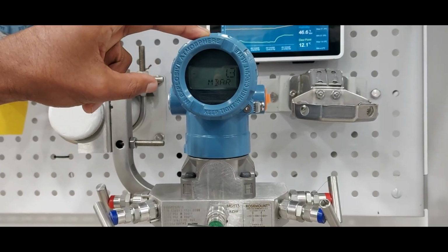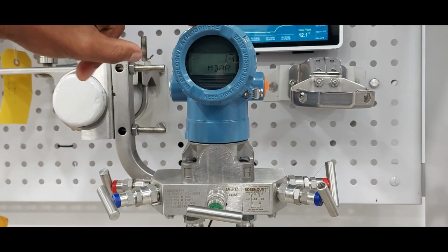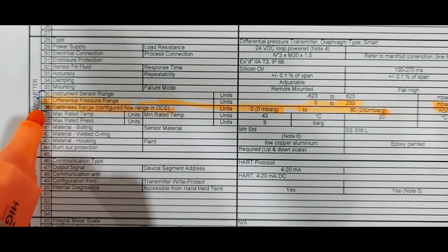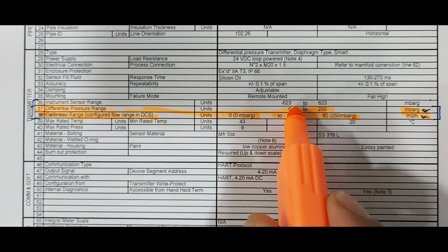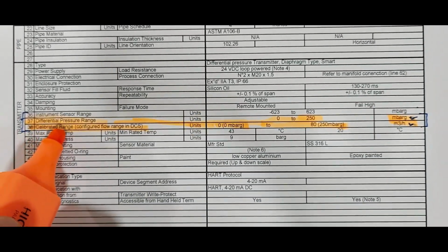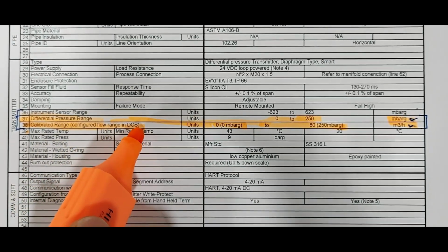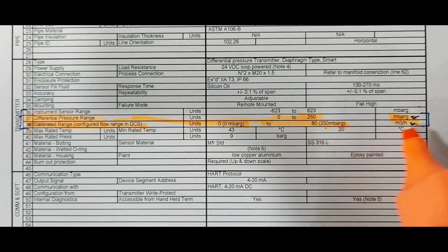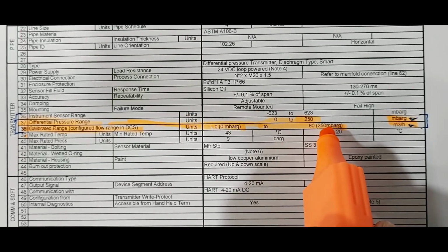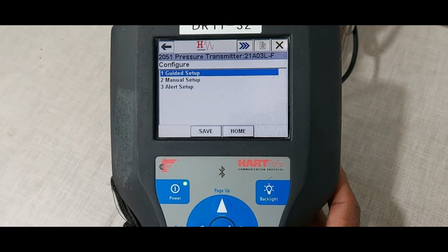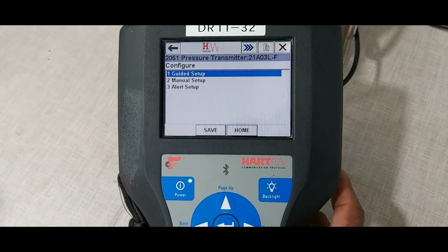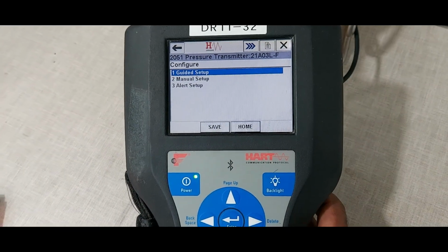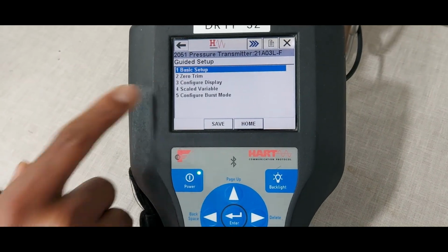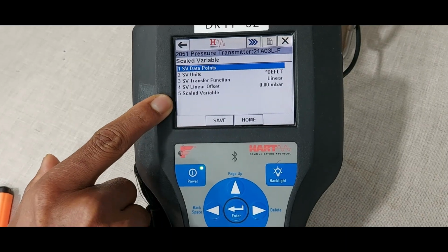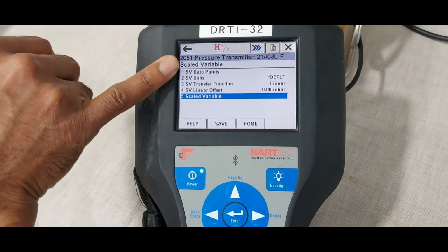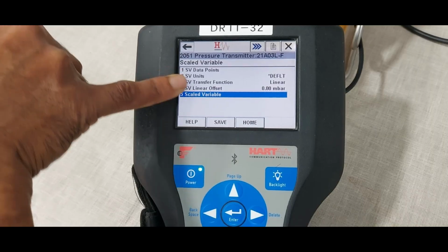Next we are doing the procedure for transmitter configuration, flow configuration and engineering configuration. The flow transmitter DP range 0 to 250 millibar. Calibrated range and configuration range of DCS: flow range is 0 to 80 meter cube per hour, DP range is the same 0 to 250 millibar. Next we are doing the configuration procedure, scaled variable. First select the configuration menu and select guided setup, and the fourth one, scaled variable unit, select it, and the fifth one, scaled variable. Default already mentioned, linear. Offset value is 0 millibar.